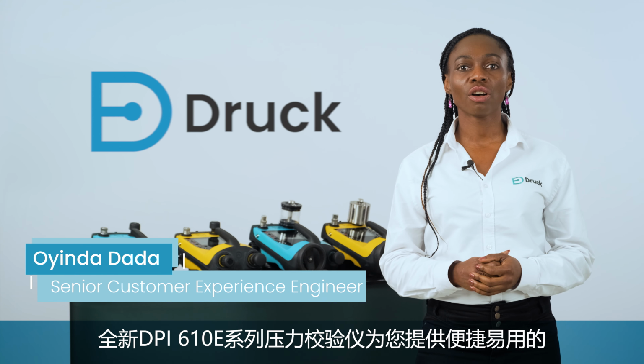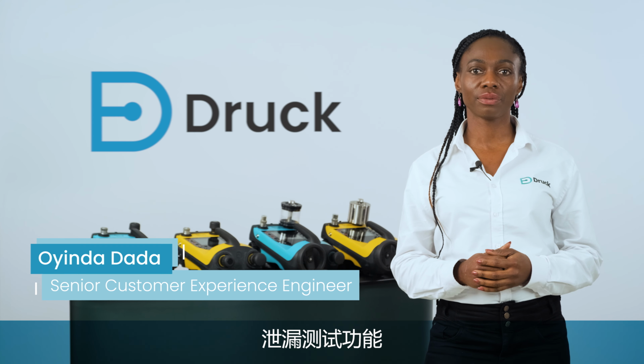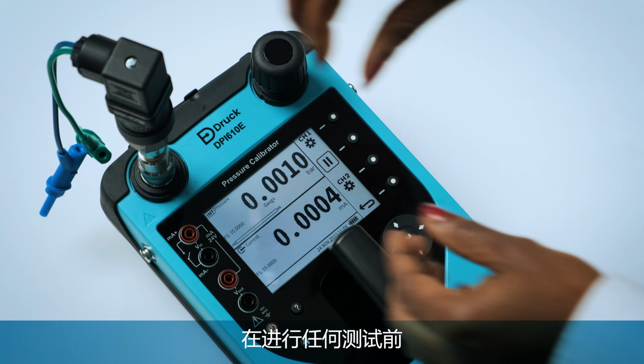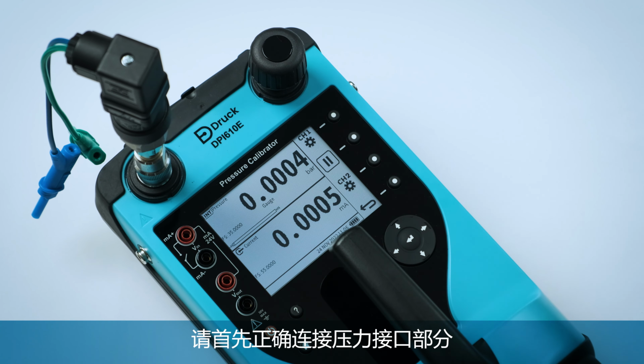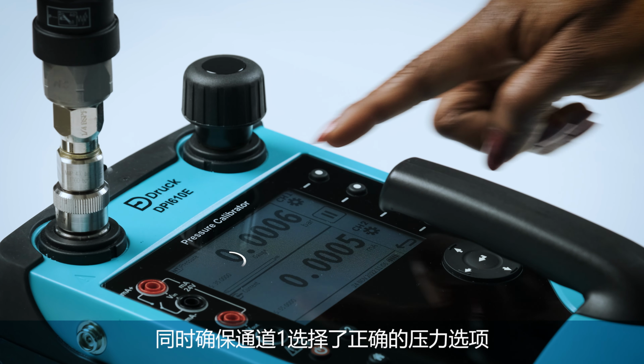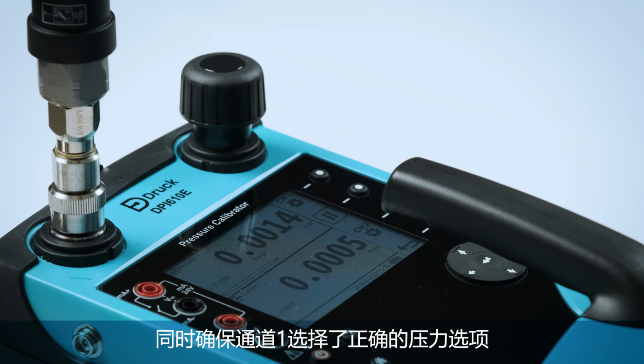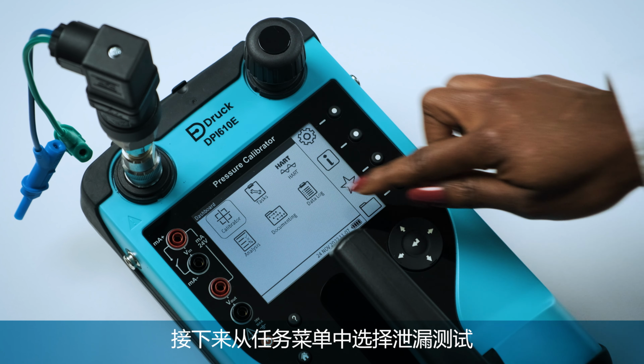The DPI610E offers a quick and easy to use leak test feature. Before starting any test, ensure all your pressure connections are secure. Ensure you have the correct pressure function selected on channel 1. Launch the leak test from the task menu.